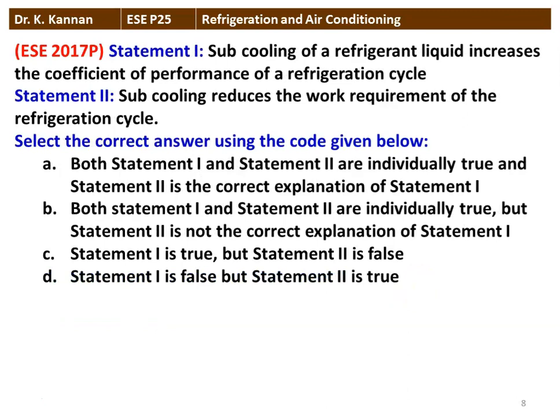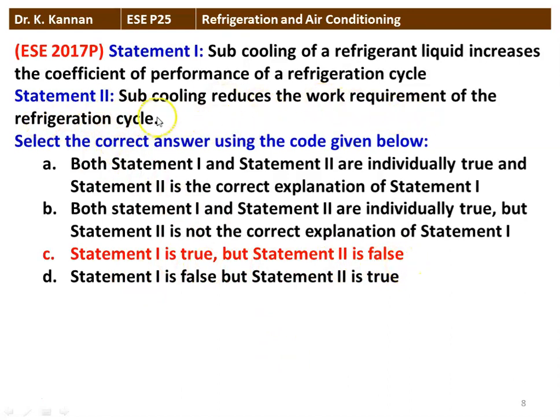The next question from the 2017 question paper — two statements: Statement one — sub-cooling of a refrigerant liquid increases the coefficient of performance of the refrigeration cycle. Statement two — sub-cooling reduces the work requirement of the refrigeration cycle. Statement one is true and statement two is false. Sub-cooling does not reduce the work requirement; instead, it increases the refrigeration effect, thereby increasing the COP of the refrigeration cycle.